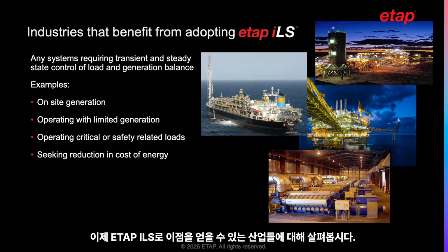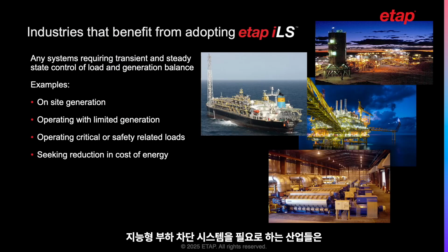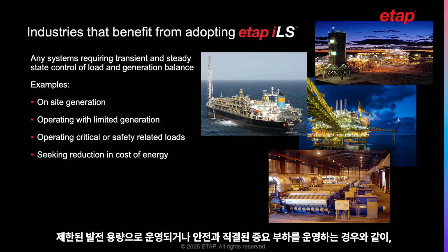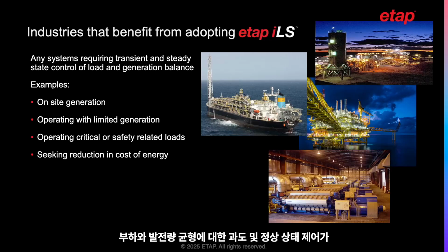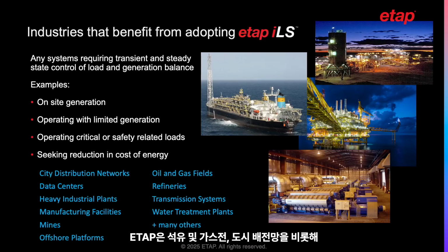Now let's look at the industries that can benefit from ETAP ILS. The industries that are in need of intelligent load-shedding systems are systems requiring transient and steady-state control of load generation balance, such as those which are operating with limited generation, are operating critical safety-related loads. ETAP has implemented ILS in oil and gas fields, city distribution networks, transmission systems, water treatment plants, cement plants, steel plants, mines, oil refineries, chemical plants, manufacturing facilities, data centers, offshore platforms, and more.